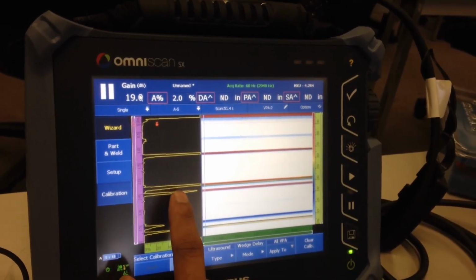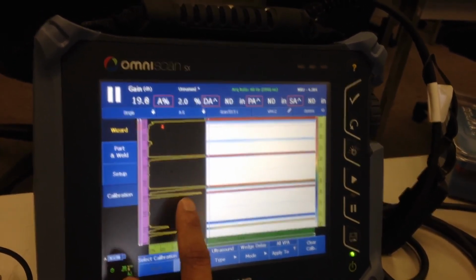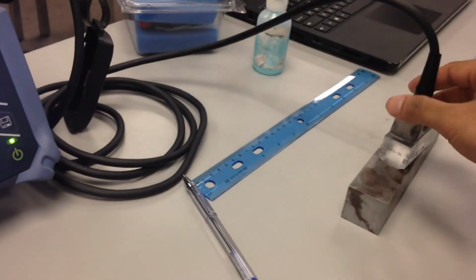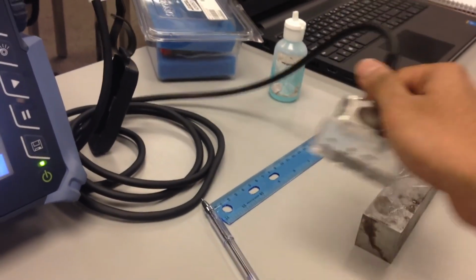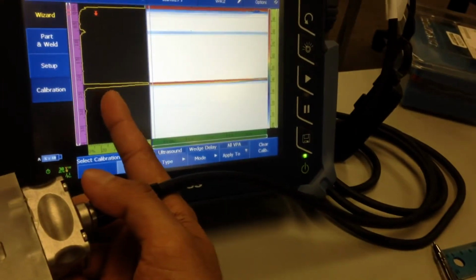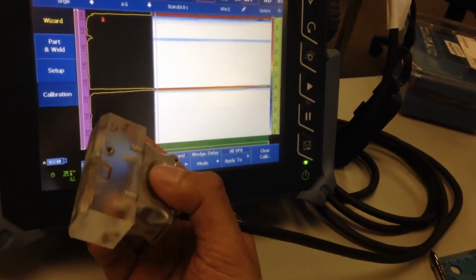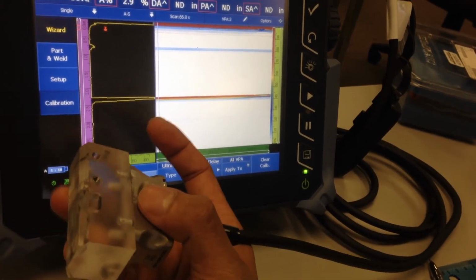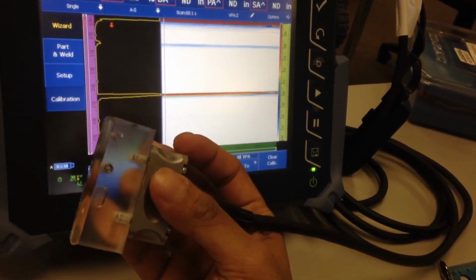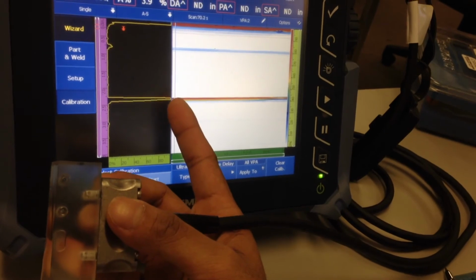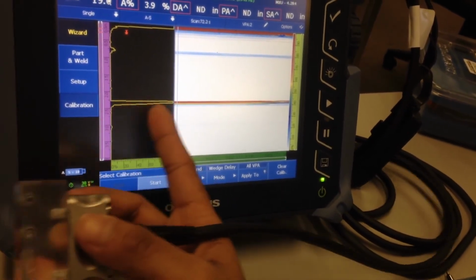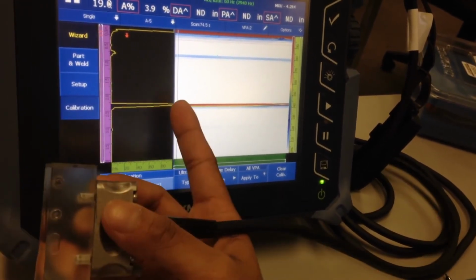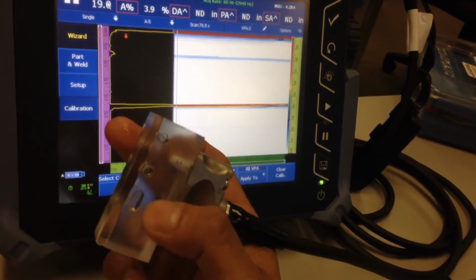Now don't confuse that signal with the second back wall. If you are confused which one's a back wall, just take your probe and wedge off of the calibration block and watch the screen for the signal that stays on the screen. So the one that stays is actually the signal coming off of the wedge and air interface, right? It's bouncing off of the wedge thickness. So that signal will always stay there in a 0° inspection with the wedge on. Don't confuse that with the back wall.